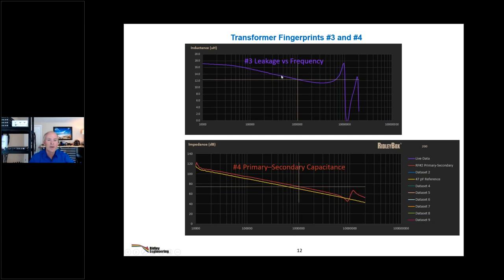Why does leakage drop? Because of proximity effects. So if you're seeing this curve dropping, that means somewhere around this frequency, before the switching frequency, proximity effects are shifting the currents flowing in the wires, moving them closer together, which is what lower leakage is all about. So that's what we're looking for here: how well is it wound? If it drops, does that mean a bad transformer? No, it doesn't—it just means proximity loss exists. It's not getting hot, don't worry about it.